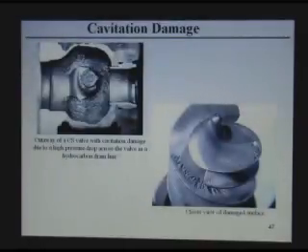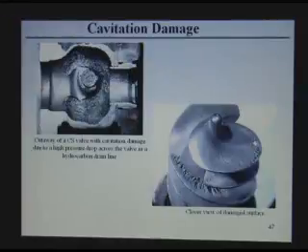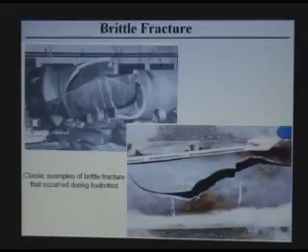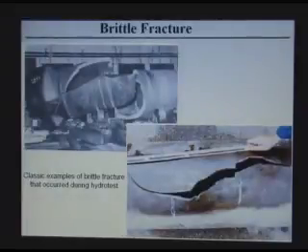This is a pump, or some, looks like a pump. No, this is a casing of a pump. Erosion and cavitation, and this is like an impeller. This is a brittle fracture, looks like from low temperature operation.